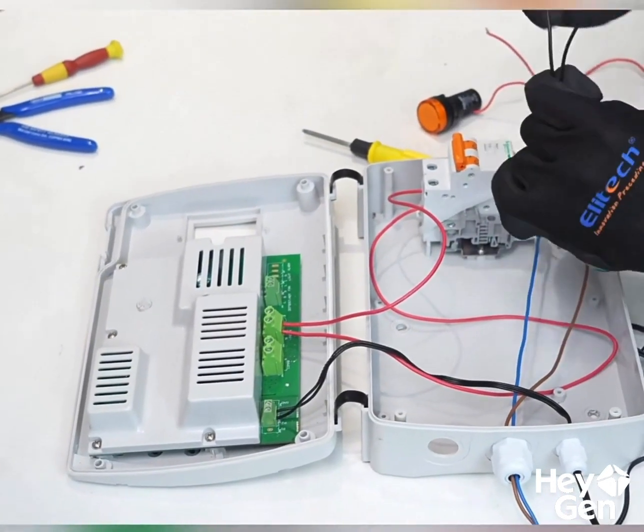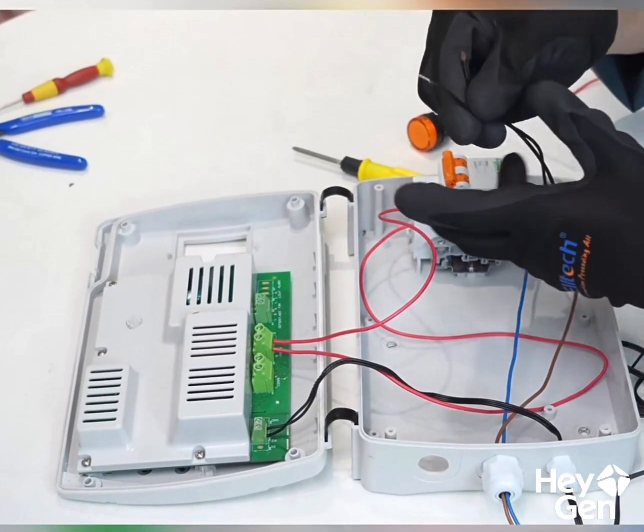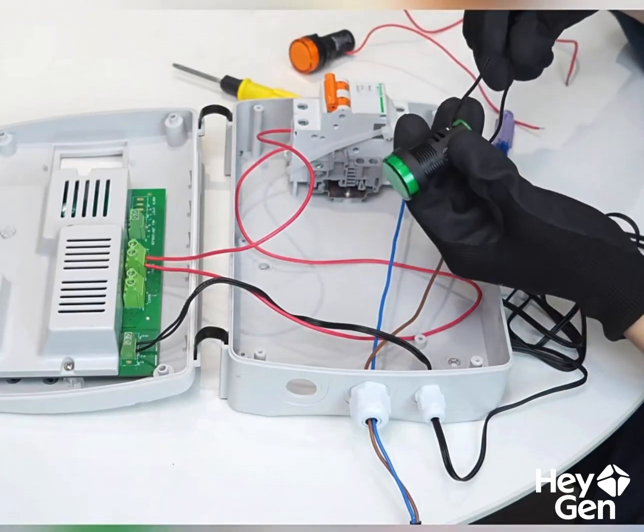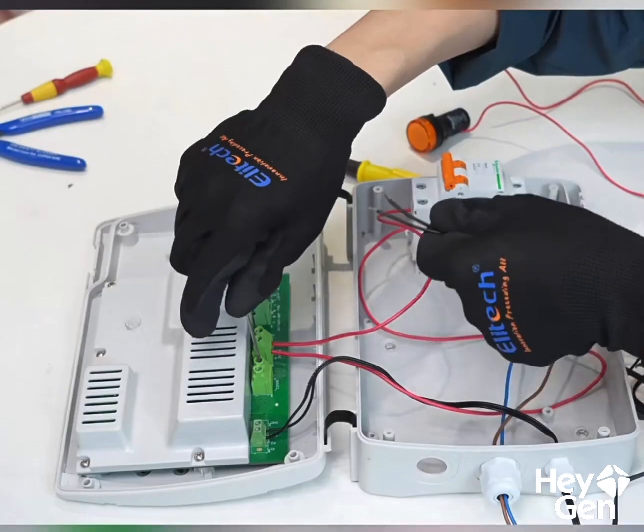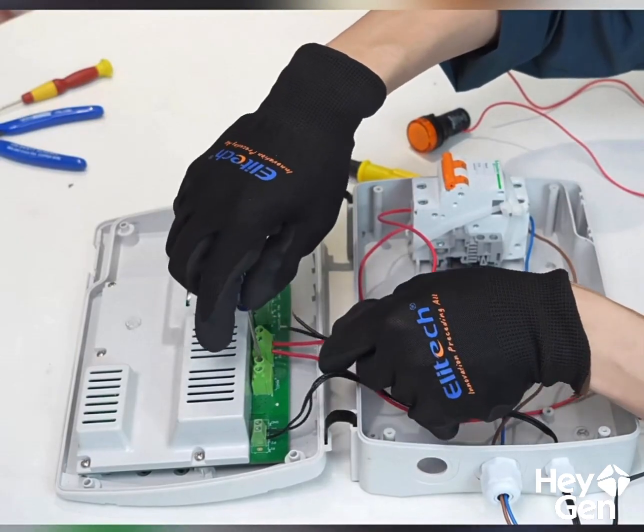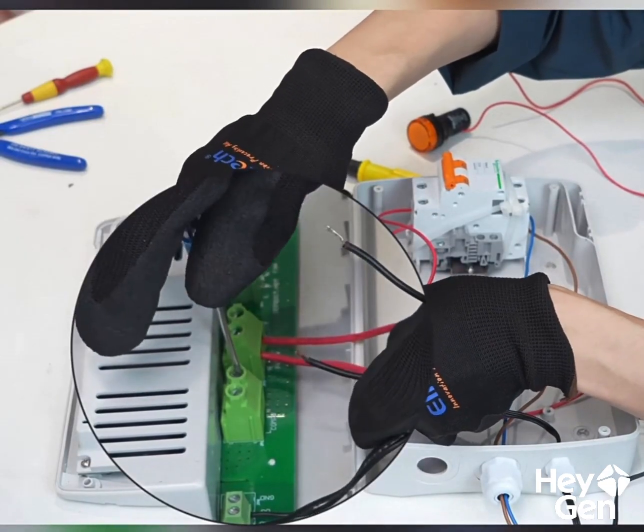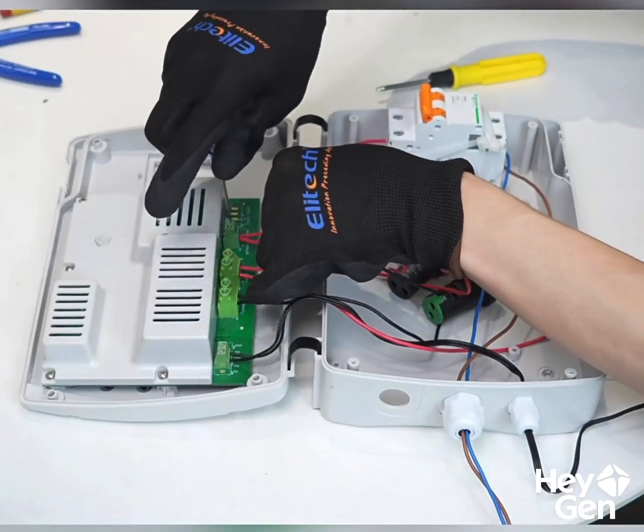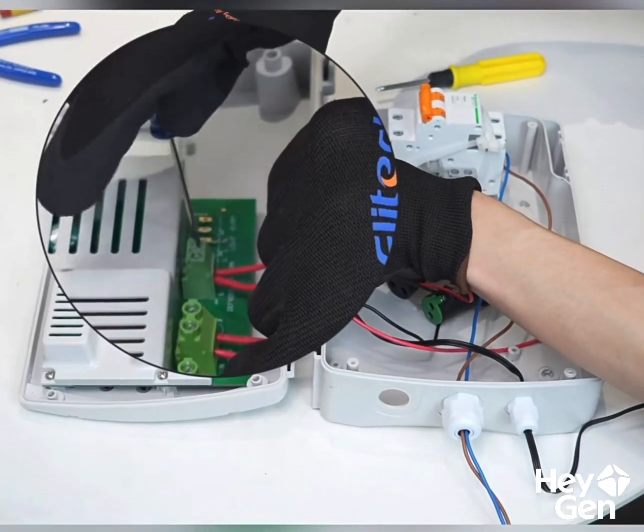Next, we'll connect the wiring for the compressor and the four-way valve. Here, we'll use 2 light bulbs to simulate the compressor and the four-way valve. Connect the 2 wires of the compressor to pins 3 and 4 on the control board. After that, connect the 2 wires of the four-way valve to pins 7 and 8 on the circuit board. With this, the wiring is complete.